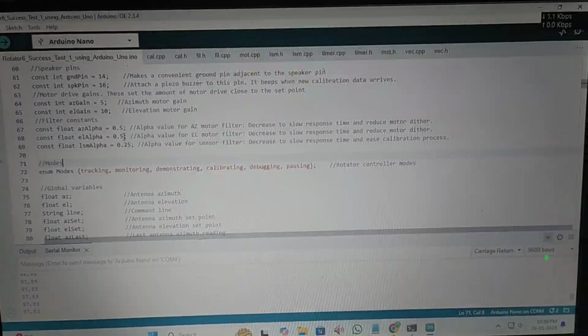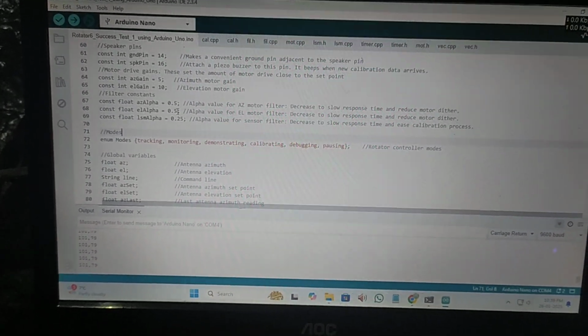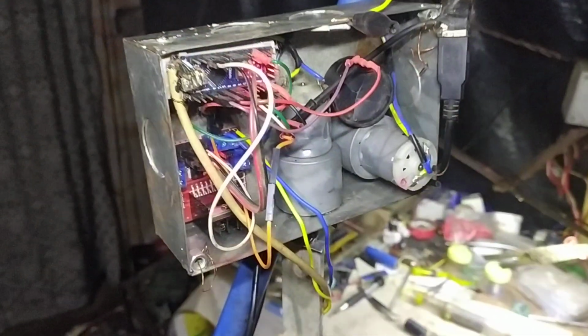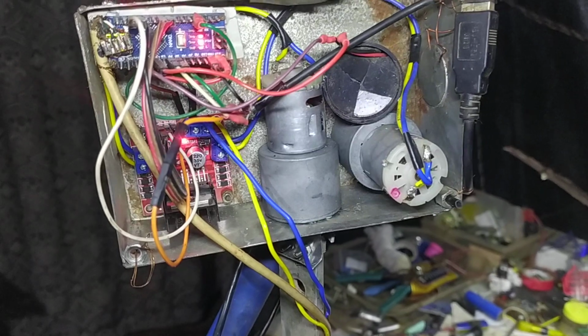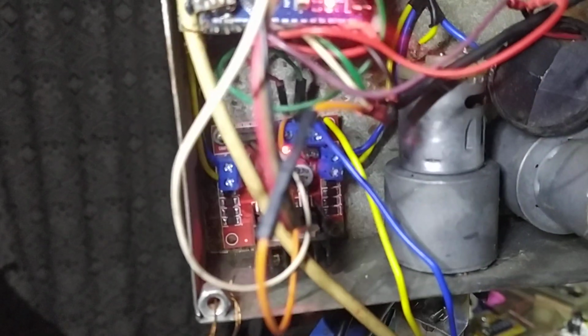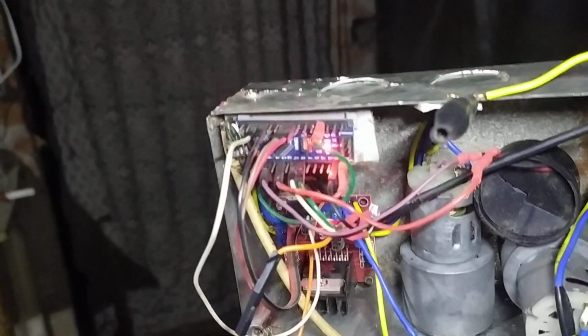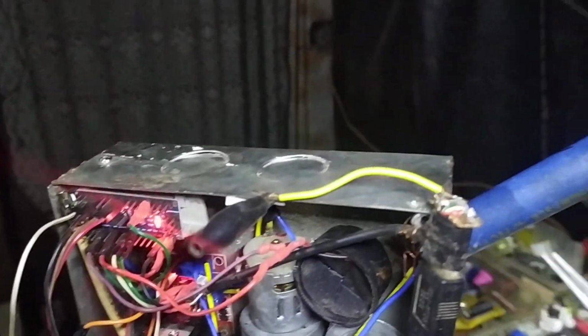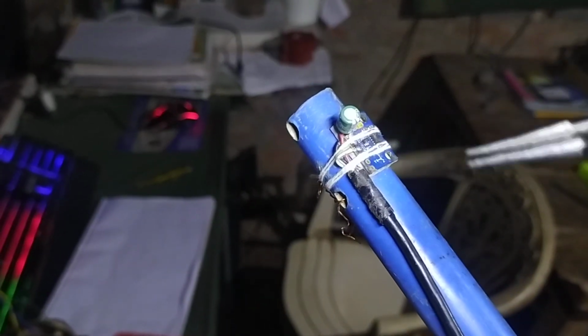So I will show you some of the design problems that I have electrically and mechanically that might get your system to oscillate. In the system that you can see I have wired everything kind of messy, but the key feature that you have to understand is all the grounds of the system must be star connected, so that the minimum noise of the system can be achieved. Here, over the sensor area, I have used shielded wire. If I can focus the camera, you can see the shield. That is the USB cable that I have cut and connected, and the ground is properly connected to the shield. That goes over and comes over here.